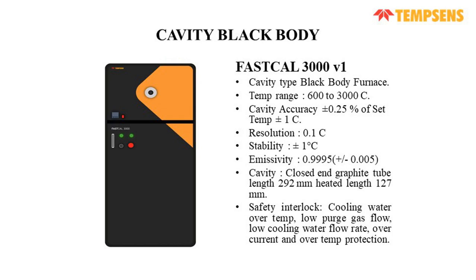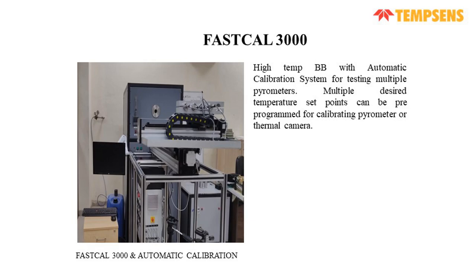It comes with many safety interlocks, and it comes with a chiller unit, because at 3000 degrees it tends to get heated. To cool the copper blocks, cooling water comes from the chiller unit. There are many types of safety interlocks: cooling water over temperature, low purge gas (argon gas purging is also given), low cooling water flow rate, over current, and over temperature protection. All these safety interlocks are given with this black body. So this is how the parameters are calibrated using the FastCal 3000.